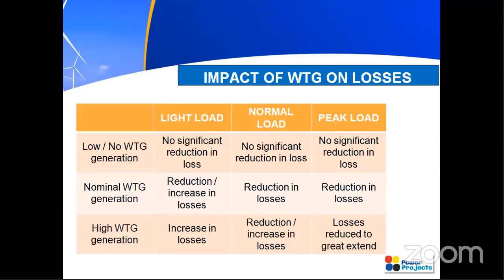Coming to the impact of wind turbine generators on losses, it depends on the load and the wind turbine generation. If your generation is low and the load is light, no significant losses will be there. If the generation is low, whether it is normal, light or peak load, no significant losses will be there. But if your generation is nominal and you have a very light load, there may be chances of an increase in losses. And if it is nominal generation and peak load, losses will be reduced.